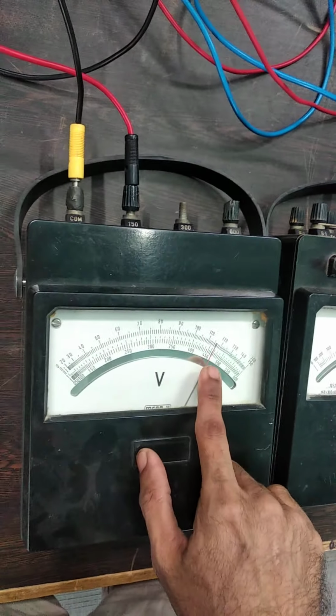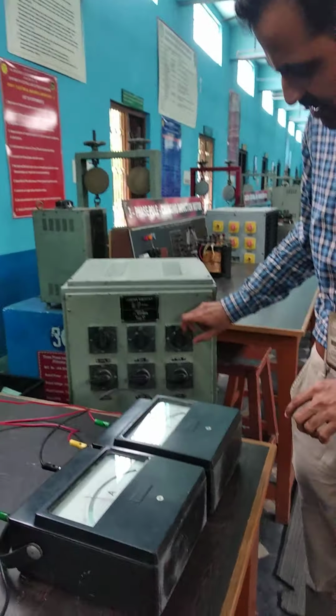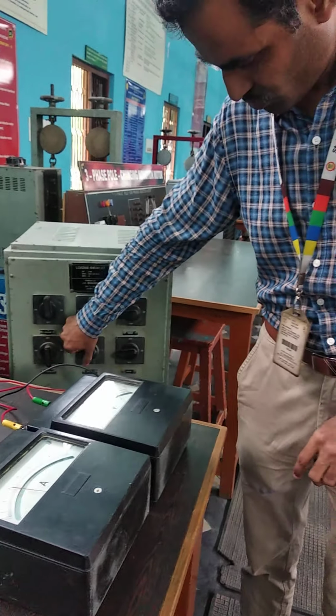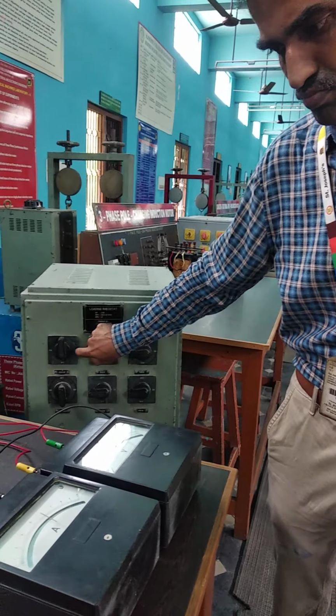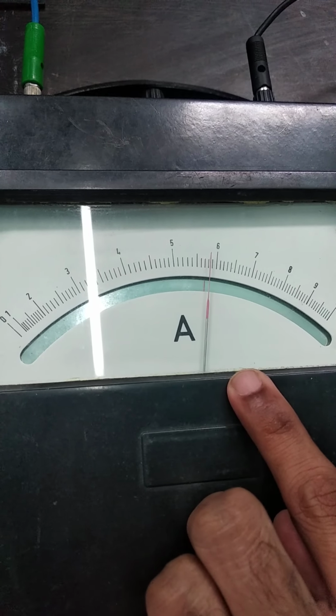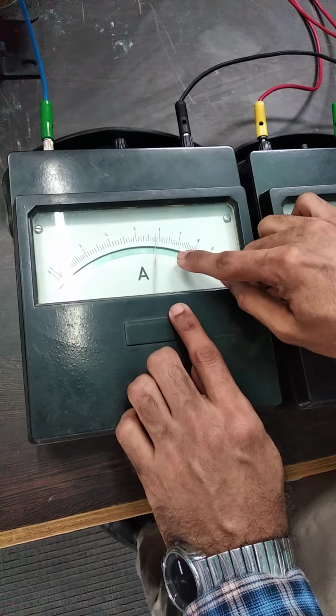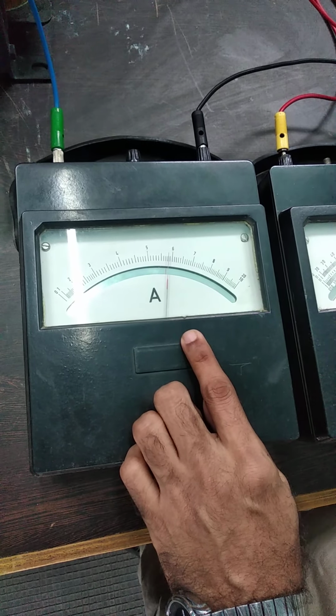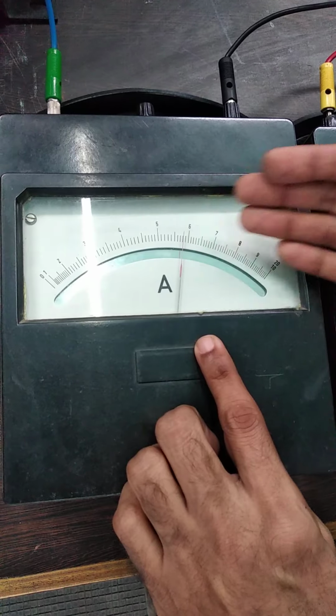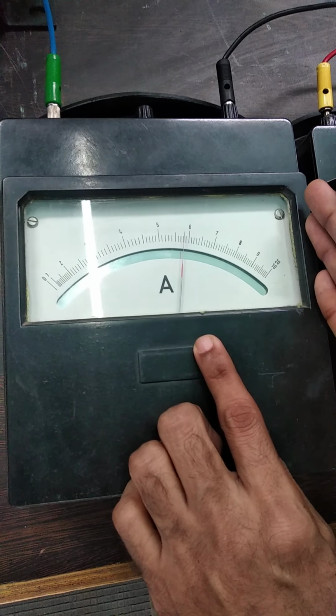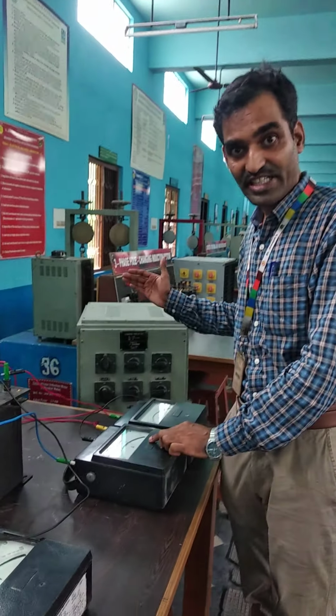Okay, so like this you can see that for every load the primary voltage comes down, so I have to increase the voltage again back to 115 volt. Then I have to step on increasing my next load. Okay, so I have to increase the load gradually. I should not increase very large extent, because you have to see that the current should not exceed the rated current. Okay, so if you increase the load all of a sudden, there may be possibility of rise of current going beyond your rated current, which is not advisable. So I have to see that the loads are increased gradually.